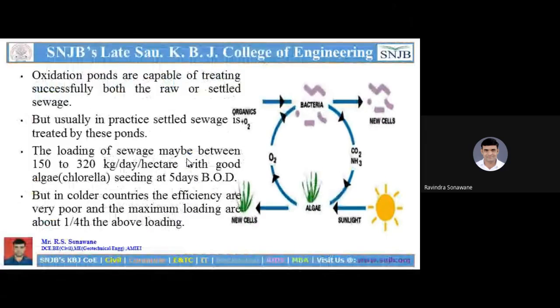Oxidation ponds are capable of successfully treating both raw and settled sewage, but in practice, settled sewage is usually treated by this pond. The loading of sewage may be between 150 to 320 kilograms per day per hectare with good algae, that means Chlorella seeding, at the 5-day BOD.